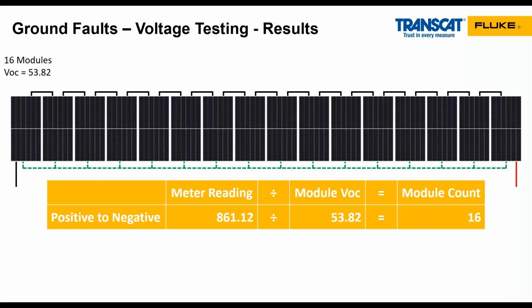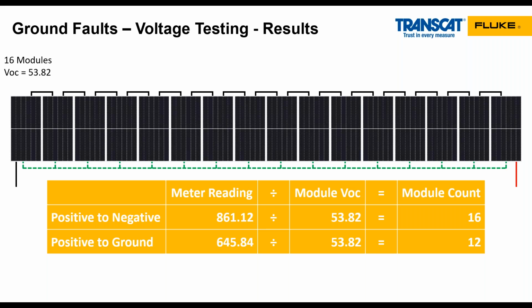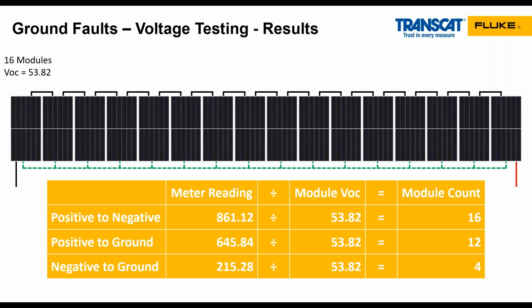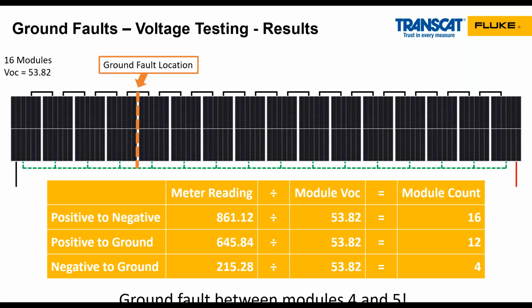Now when I look at my results, my positive to negative 861 volts divided by 53 volts gives me a module count of 16, which is what I would expect. This is not going to be exact, but it's going to be pretty close. When I divide 645 by 53, I get about 12 modules. And when I divide 215 by 53, I get about 4 modules. What this means is that I have 12 modules between the positive and the ground fault, and 4 modules between the negative side and the ground fault, which means counting from the negative side, I've got a fault between modules 4 and 5.